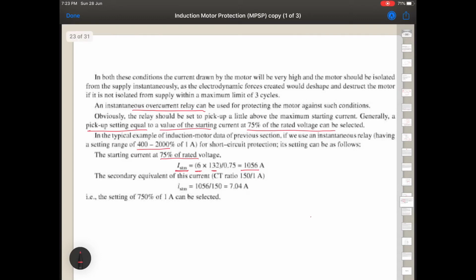Just as an example, I'm taking an analogous case. If you have 7.5 ampere for 7.5 volts and 10 ampere for 10 volts, then we are taking this current and predicting 10 ampere. The current is proportionally increasing as the voltage is increasing. Based on Ohm's law, V is equal to IR, current is proportional to voltage. Now we don't want to take the current during short circuit, which will be too high, so we are limiting to the current at 75%, and because the relay cannot handle too high a current, we are taking 75% of the rated voltage and doing the calculation.